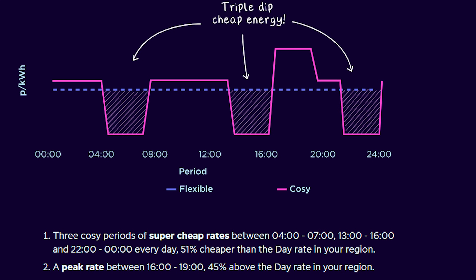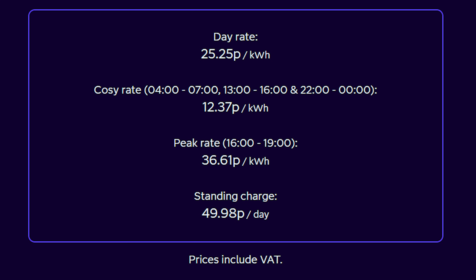But as I mentioned, COP isn't always what you pay. For example, if you're on Octopus Cozy, you get 12p from certain hours of the day, and between four and seven you're paying a lot more than 12p. So what you might want to do is run the heat pump very hard just before four o'clock, get it really warm in your house to store heat in your insulated home, turn off between four and seven, and then reheat later.